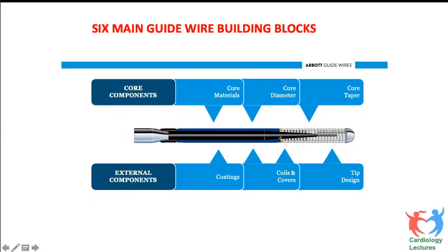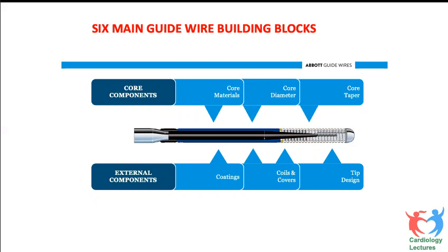The core material is either stainless steel, high tensile steel, or nitinol — the most common materials. Then there is core diameter: the larger the diameter, the more weight at the tip and less prolapsing. Third is core tapering — whether the core carries the same thickness all the way to the tip. If it does, there is more penetrability but less steerability and less ability to slip through a lesion.